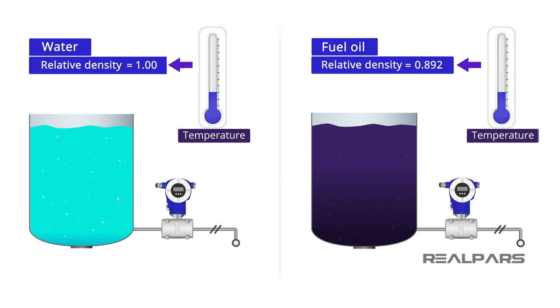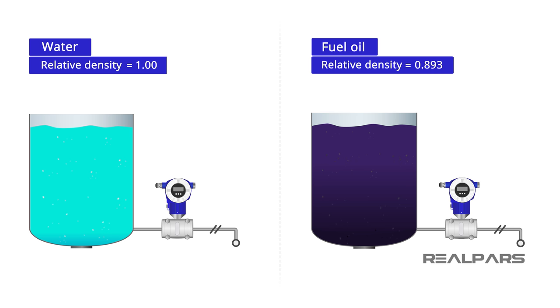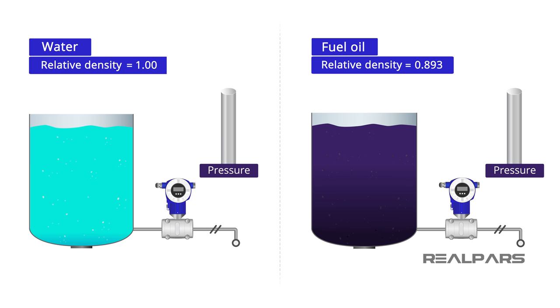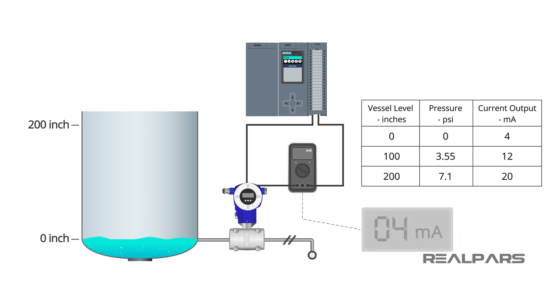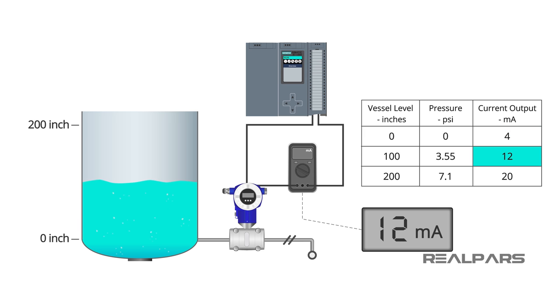The relative density of most liquids will change with temperature. For the sake of simplicity, we will ignore the effect of temperature for now. Interestingly, when the vessel is full at 200 inches, the pressure developed is much lower because the liquid has a low relative density. That is a critical consideration when calibrating the differential pressure transmitter, which is calibrated to produce 4 to 20 milliamps for a liquid level range of 0 inches to 200 inches.